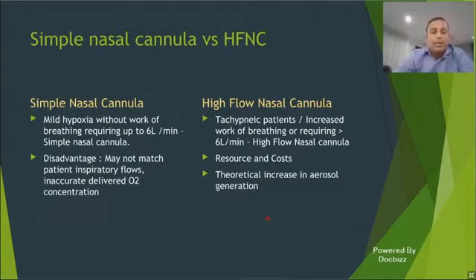So what that does is, because you're only providing 6 liters per minute of oxygen, and when the patient is breathing, say 20 liters per minute, the excess flow comes from the room air. So that dilutes your oxygen concentration, and you're never actually giving 6 liters of oxygen if the patient is breathing 20 or 30 liters per minute. Now that's where the high flow nasal cannula comes in.